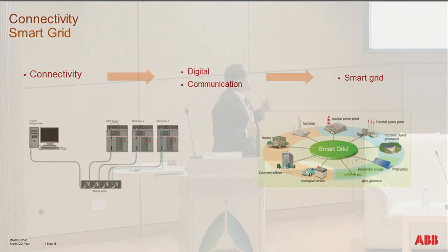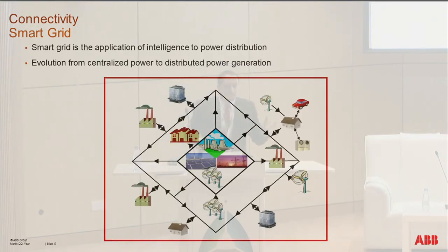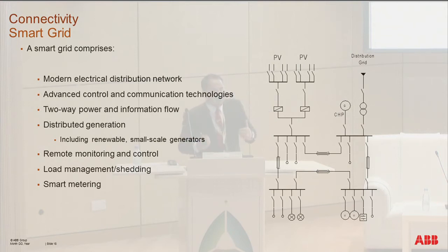After discussing the communication protocols, this is a very important function which is mainly required for applying a smart grid. The smart grid is an intelligent grid, where the low voltage devices, specifically the low voltage circuit breakers, must be intelligent and provide digital communication to be connected in the smart grid. The smart grid is an intelligent application of intelligence to power distribution, and it comprises different parts. It's a modern electrical distribution network. We have different sources of power, through utility, PV, solar cells, and generators. So we must have digital communication, remote controlling and monitoring of the smart grid, smart metering, load management and load shedding. All this we will see in the coming slides, and how we can provide it using ABB circuit breakers, EMAX2 specifically.